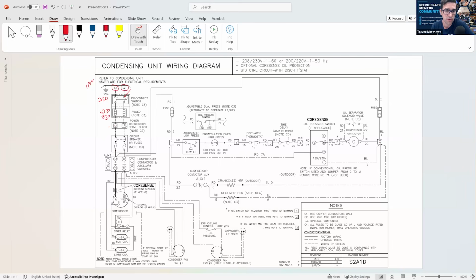This is so important. There's a power distribution terminal block. You check on the L1 there, should say 230, or it could be give or take, it could be 228, 220, depending on the voltage coming in, but I'm just doing an example here. Now I do it on the upstream side of the circuit breaker. Even if it's off, if it's open, we should get 230 on the upstream side. And if we went down to the downstream side, what will we get if it's off?